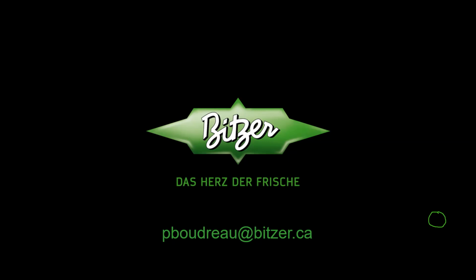And yes, I recommend them. Actually, I recommend them on every two-stage compressor you put in. I recommend them even on single-stage compressors that require head cooling fans. Anywhere the compressor requires auxiliary cooling, it's a nice way to ensure that your auxiliary cooling works. So I highly recommend it. Yes, it will fit on all the two-stage compressors.